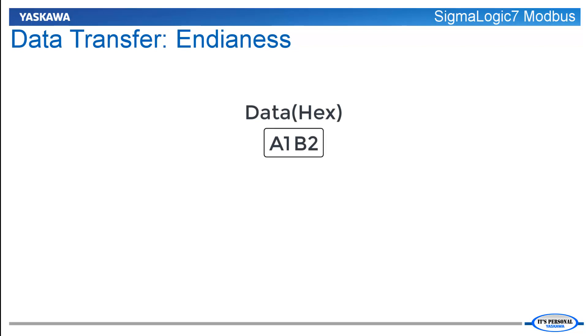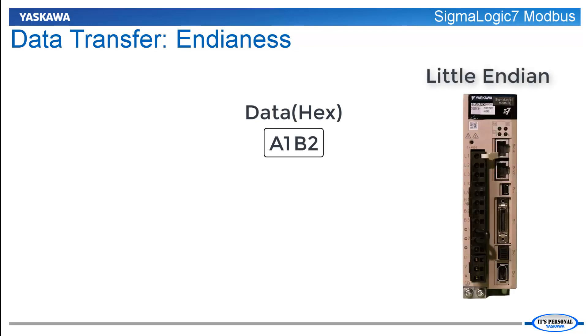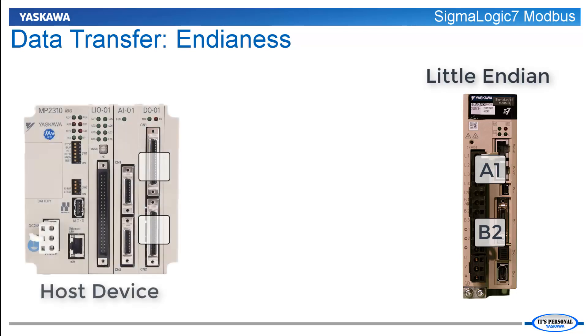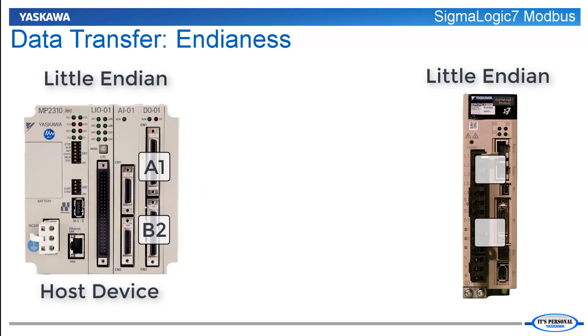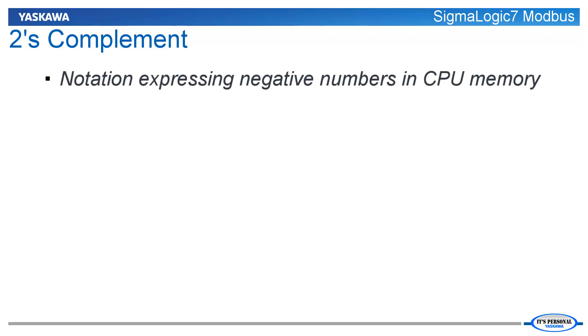The Sigma Logic 7 Modbus stores data in little-endian format, meaning the least significant byte of data is placed in the lowest number register, sometimes called the base register. All provided documentation will reference the data in little-endian format. If the host device also stores data in little-endian format, the user will not need to rearrange the data. However, if the host device stores data in big-endian format, then data sent across the Modbus TCP interface will be stored with the most significant byte in the lowest number register. This reordering of data in memory requires extra handling by the user, and examples will be described later in this video.